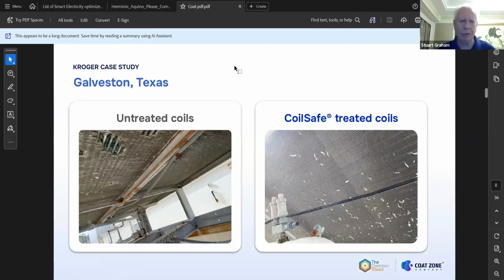Here's another great example. This is a Kroger grocery store. They have a store in Galveston Bay that literally overlooks the bay, right across the road from the bay. They installed 6 refrigeration condenser units on their roof. 5 of them we coated, 1 they forgot to get coated. After only 3 years of oceanfront exposure, this is the untreated coil, as you can see, destroyed, had to be replaced.